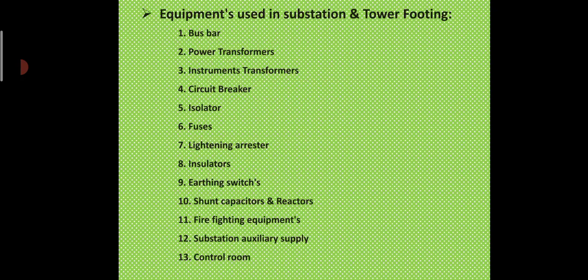Now, circuit breaker. A circuit breaker is a device which can interrupt a section or a circuit automatically if abnormal or faulty conditions exist in that section. Under normal operating conditions, the contacts of each pair close on themselves and the circuit breaker is said to be closed. In the event of any abnormal situation, the movable contact of each pair is made to open against spring forces by mechanical devices through a trip circuit energized by a battery. The trip circuit is activated by one or more relays which sense the abnormal conditions. The relay and the circuit breaker act as complementary components of protective devices.